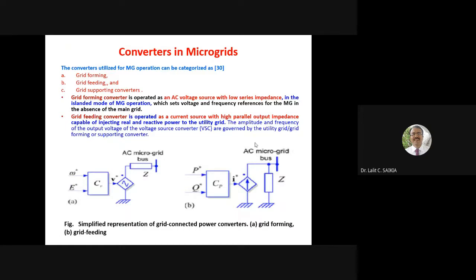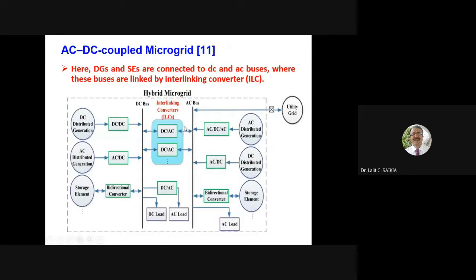So converters now play an important role, since here see DC DG, this is mainly say PV system, AC DG with energy conversion system. This system, whatever the output voltage, that is fluctuating in nature, intermittent in nature, not fixed. We have to make it fixed at the reference voltage of DC and AC bus. Now to control this voltage, it is required that this converter should be controlled. This power electronics converter should be controlled.